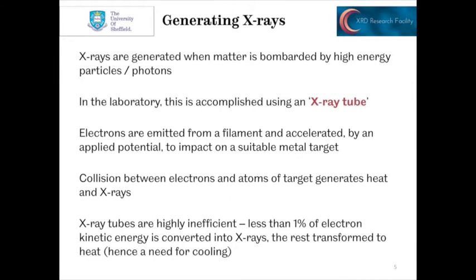X-rays are generated when matter is bombarded by high energy particles or photons. In the lab, this is accomplished using a device called an X-ray tube. Electrons are emitted from a filament and accelerated by an applied potential to impact on a suitable metal target. The collision between electrons and atoms generates a lot of heat and a few X-rays. X-ray tubes are extremely inefficient — less than 1% of the electrons' kinetic energy ends up getting converted into X-rays. The rest is transformed into heat.